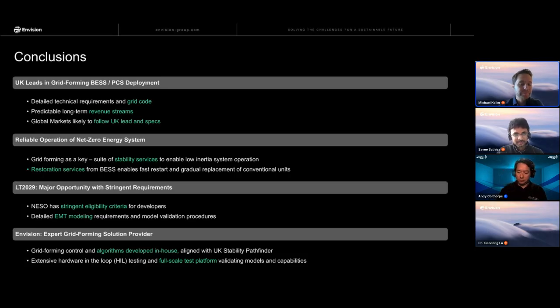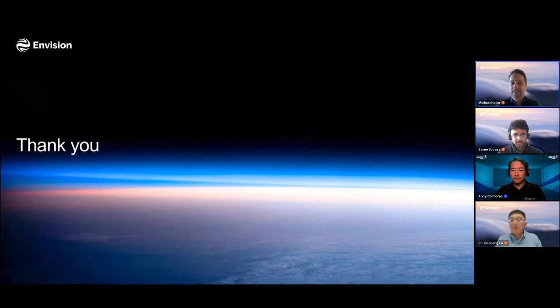Which leads us to LT2029. It's obviously a major opportunity for UK BESS and players in UK battery storage, but it has very stringent eligibility criteria. So it's important that the modeling is based on proper simulation, hardware-in-the-loop and real-life testing. We believe that's exactly where Envision can provide value. With our experts, who have developed these grid forming algorithms and aligned all of our performance with UK criteria, we can be the right partner to enable this EMT modeling in compliance with NESO, to make sure the project is eligible and in the end does provide the stability services as required by the system.